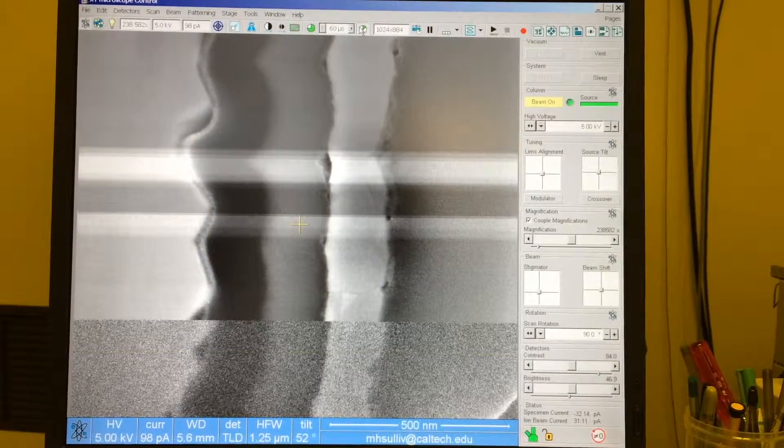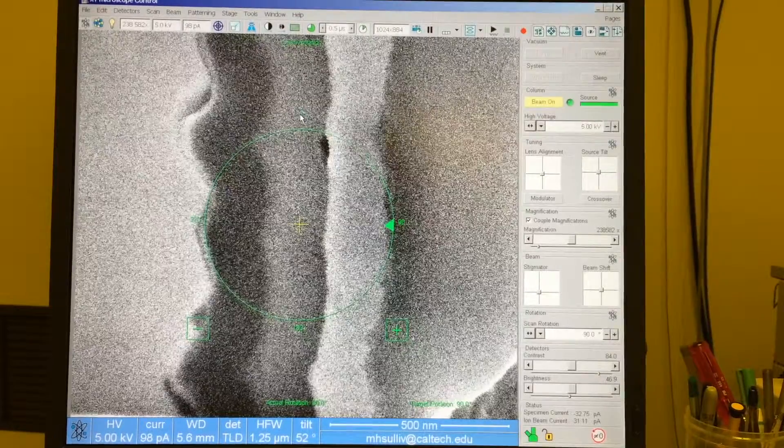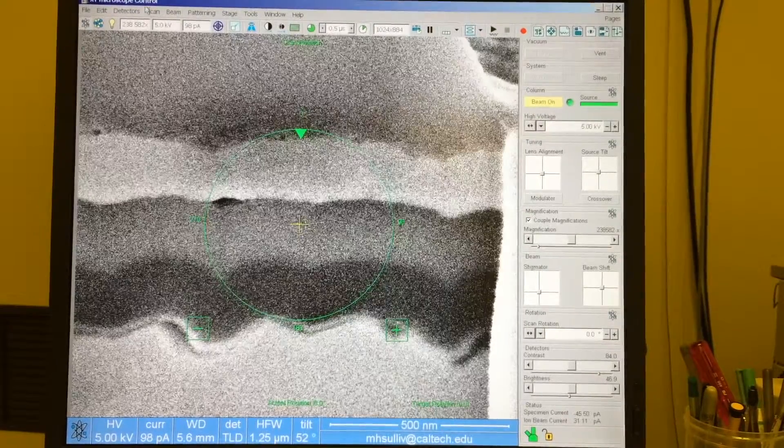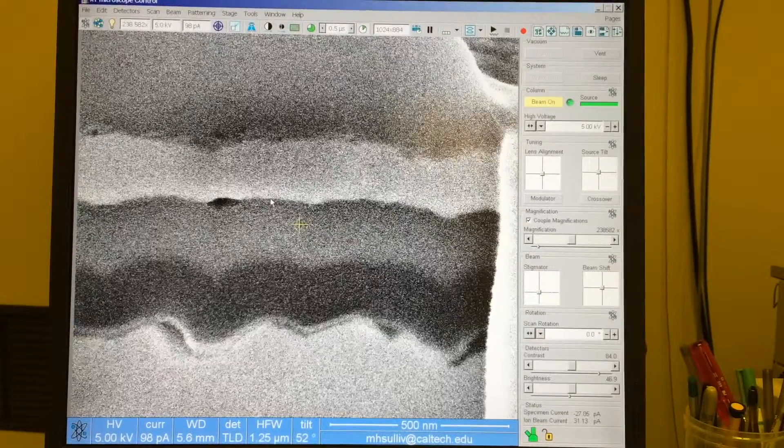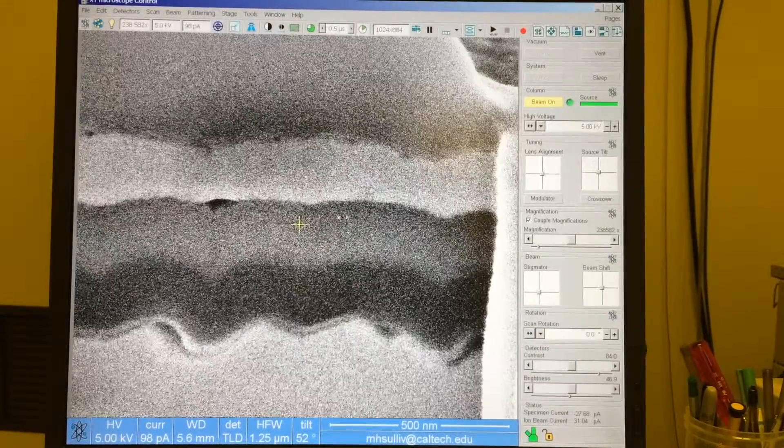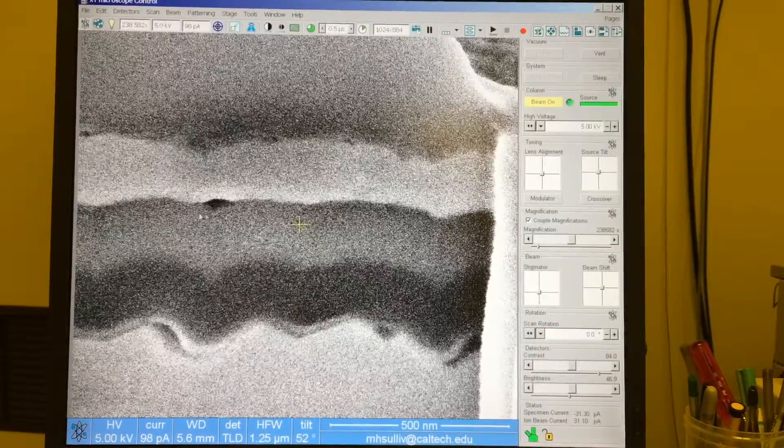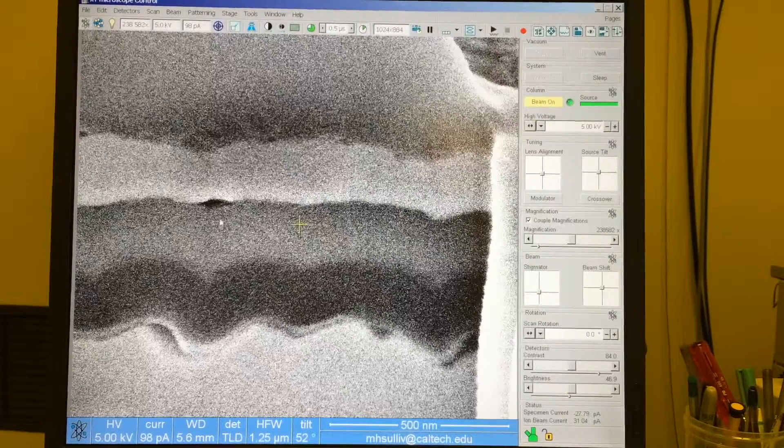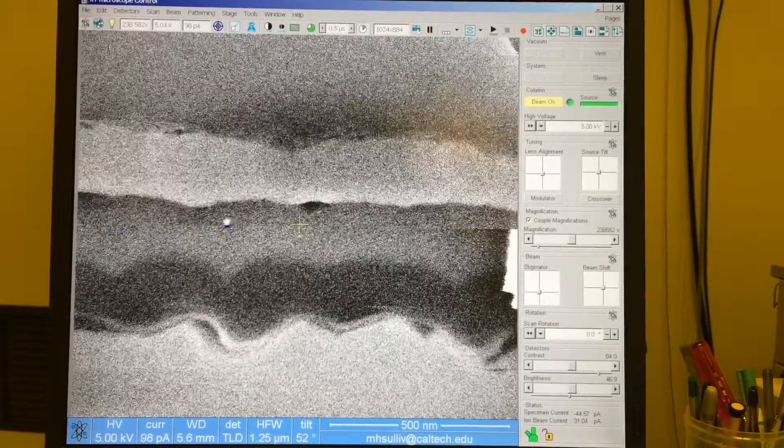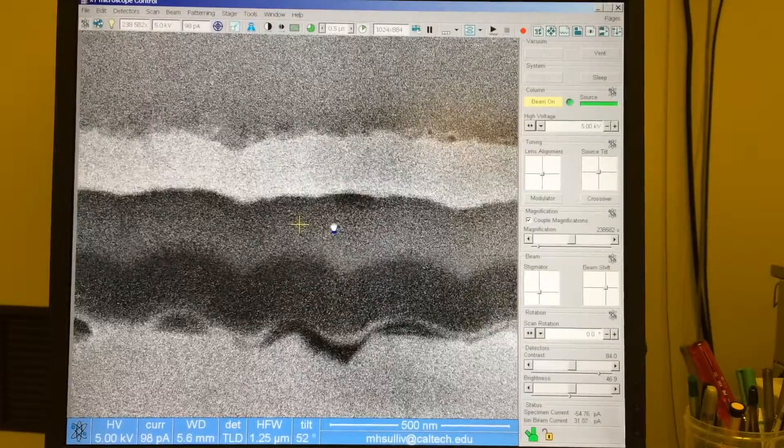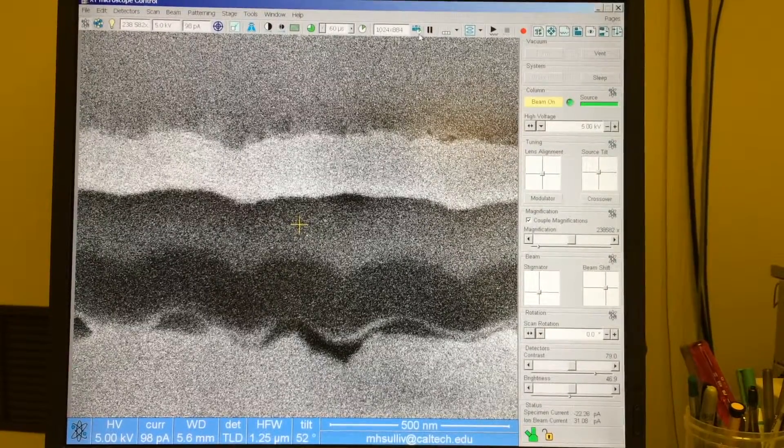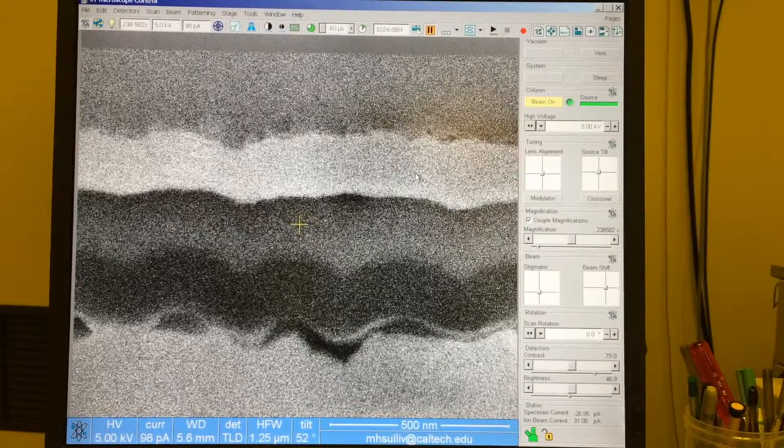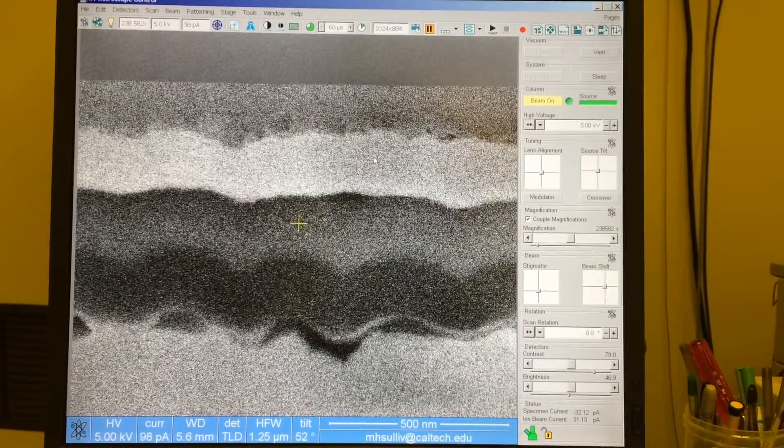So I can turn that off. I'll go back to a short dwell time. I'll go back to zero degree scan rotation, and then turn that off. And now we've been scanning here for a while. We did our alignment here. We adjusted brightness and contrast. So we've probably put a little bit of beam damage onto it. There's going to be some gray boxes. So we want to move away from this. So I'm going to, rather than double clicking, which would move the stage and might disrupt the focal plane as it's contacting the surface, I'm going to use beam shift to just shift us horizontal away from that area. And so now I'm on a nice fresh spot, and I'll go to my 60 microseconds, and then remember to press pause.